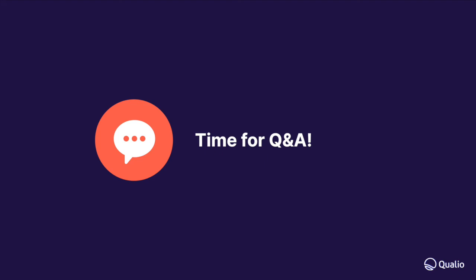And Richard, there's another question from the risk assessment. It's around adding detectability in the current risk assessment. Okay, so in terms of detectability, we're covering that under the FMEA section. So we've tried to stay true to the ISO 14971 standard and remained only with the two measures and left that detectability into the FMEA section. Both can be used together. So you do have a choice to actually have both types of assessment running within your product.